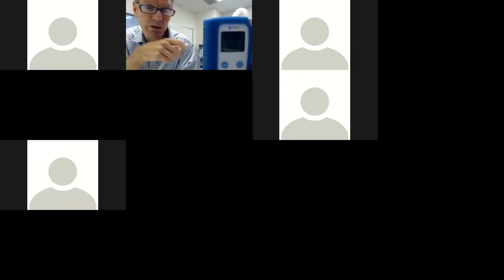And why do you think it's 20.8%? Atmospheric air. Atmospheric air, very good. That's right, because I've got the tubing on, but it's not connected up to anything. Can you see the second number below the oxygen concentration? What does that say? 0.0. What that tells you is the flow rate. At the moment, this oxygen analyzer is not on any flow. It's just open to air, so there's no flow through it. It's just measuring atmospheric air. So when you turn an oxygen analyzer on, it should measure something like 21% or 20.9%, and something like 0 because it's not attached to any flow.